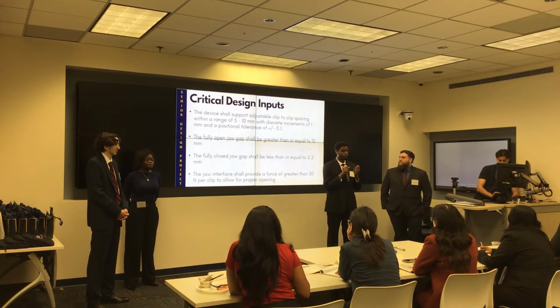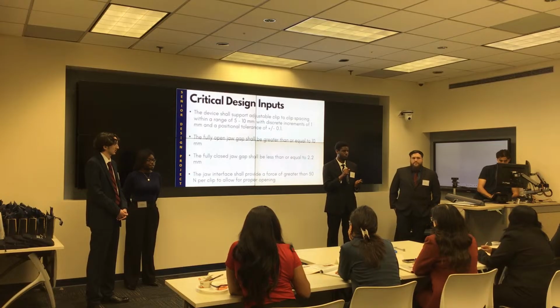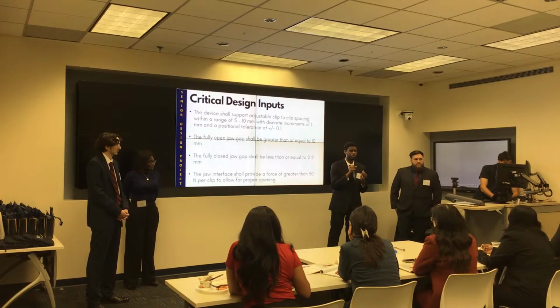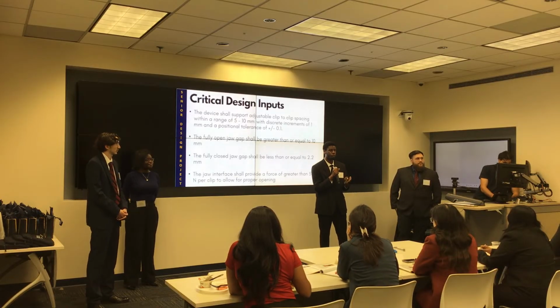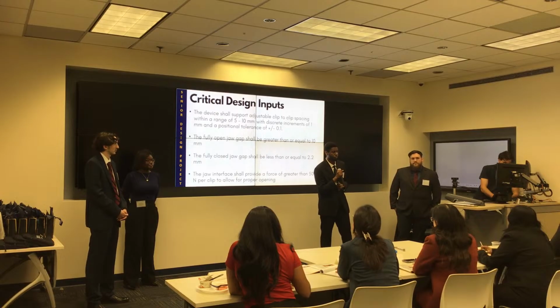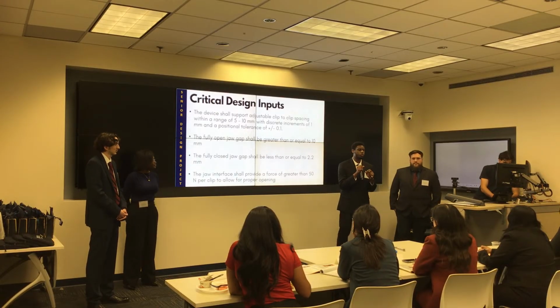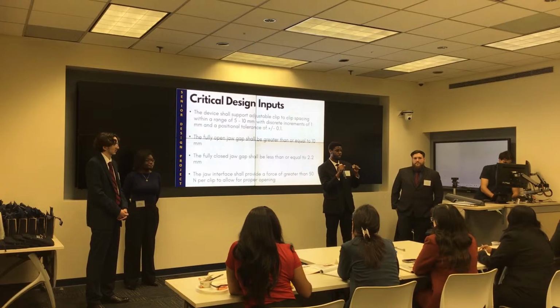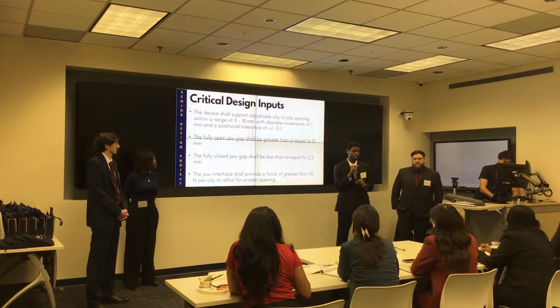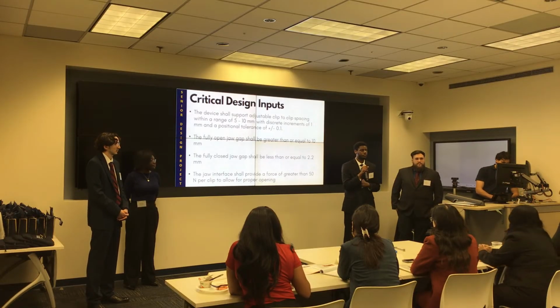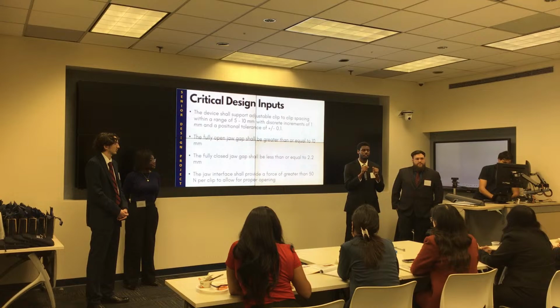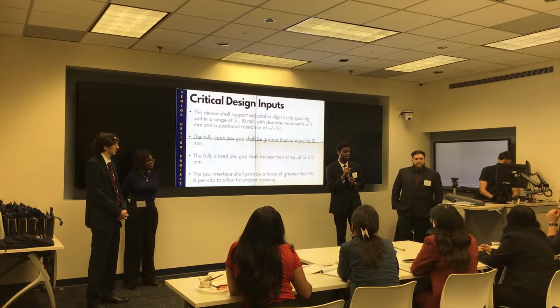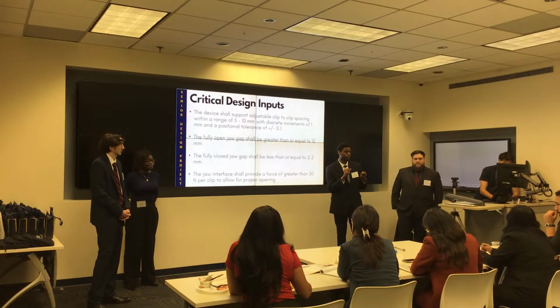So we translated these into our design inputs. We decided to design a device that would have a jaw with the proper clearance to fit 2 vessel clips and allow the vessel clips to be placed between 5 and 10 millimeters apart with 1 millimeter intervals in between. We also decided to create the jaw with proper clearance so that when the clips are placed, they won't snag on the clips, needing a 10 millimeter clearance in order for that to happen. We also designed the device so that 50 units of force would be sufficient for applying the clips, since this is the force needed to both actuate the clips and apply them to the vessels.